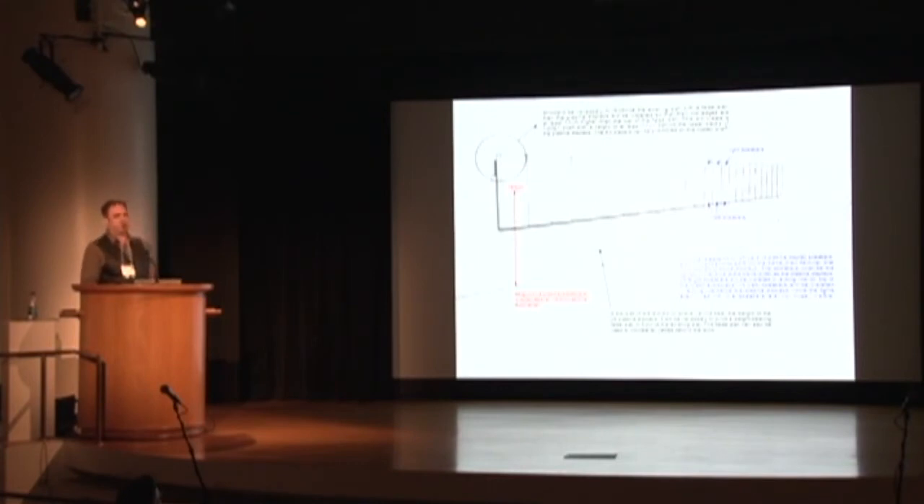This is a great piece to talk about in terms of requirements. There are 25 monitors — that's a lot of weight on that wall. Candace is experienced with this work and has very clear descriptions about the technical requirements. When you want to hang five projectors in a gallery, is there more than sheetrock in that ceiling? Is there a way to suspend that amount of weight? It's not just the projector — it's the pole holding it. And how much electricity do 25 monitors take? Each one is pretty efficient at about 2.3 amps, but altogether you need four or five circuits of power, which may or may not be easy to get.